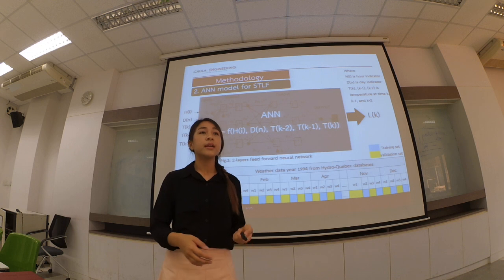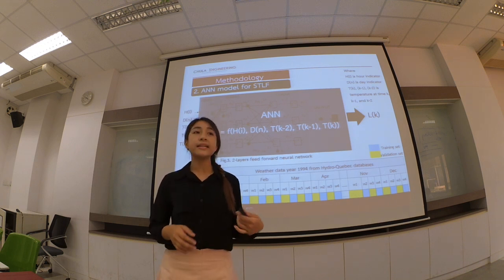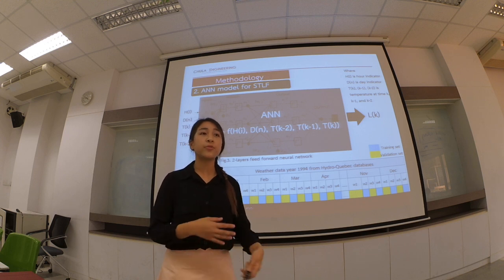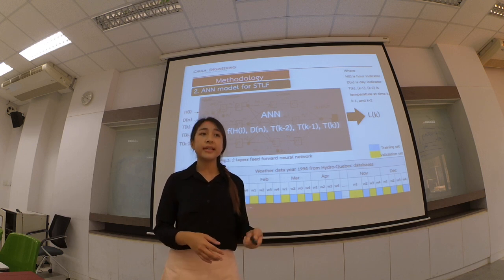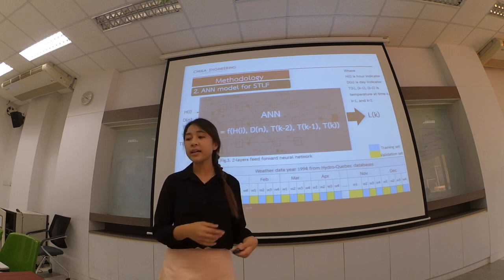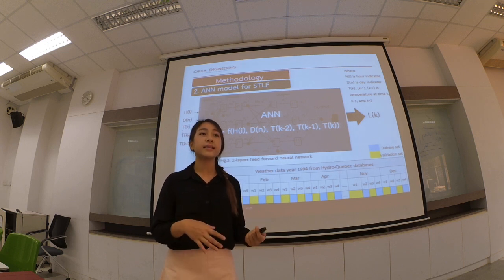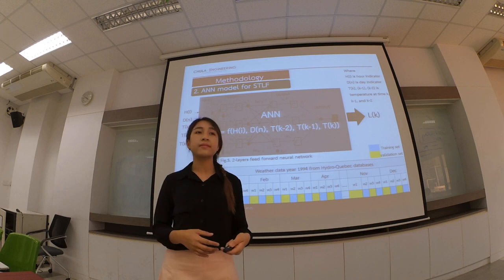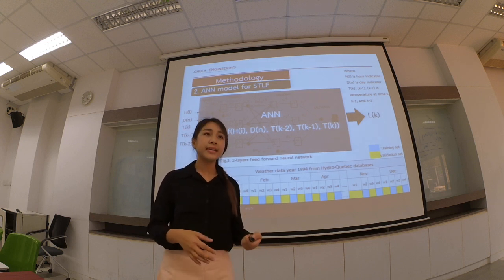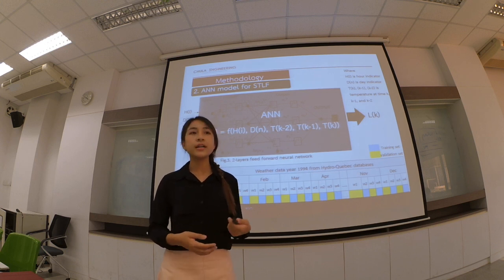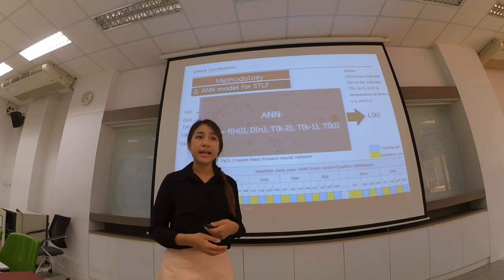Step 2: The ANN model for short-term load forecasting. In the gray box, you can see the artificial neural network for this forecasting. The inputs are the hour indicator, day indicator, and temperature at time steps K-2, K-1, and K. The output of this model is the load at time K. The data for training and validation came from the Hydro-Quebec database in the year 1994.